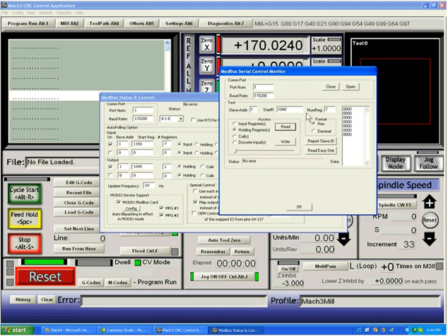and you can see that we can still read from 1040, although it doesn't make any sense to do so because they are registers meant to write data to, and they're all set to 0 at the moment. If we hit write, we have no error listed, and we did write data to the board. You could set a bit pattern into these hex bytes and hit write, and on Peter's board, inputs will become active immediately when you hit write because the terminal strip will then reflect what was in these boxes. So this is a good way to test a Modbus device.